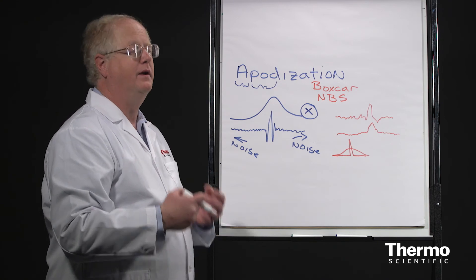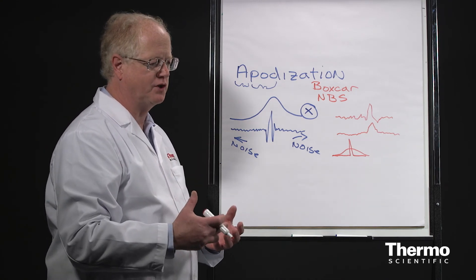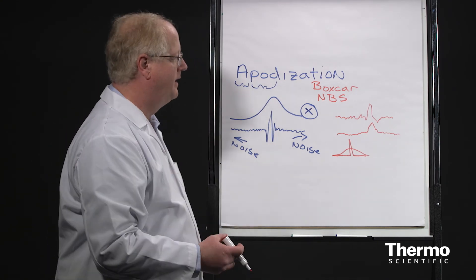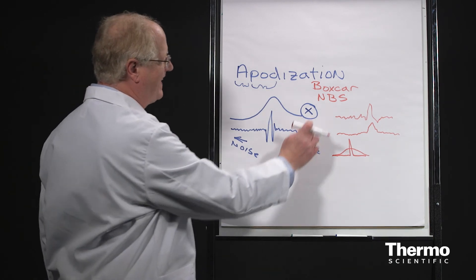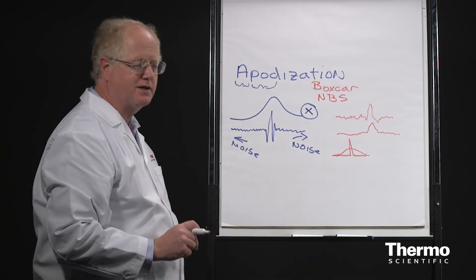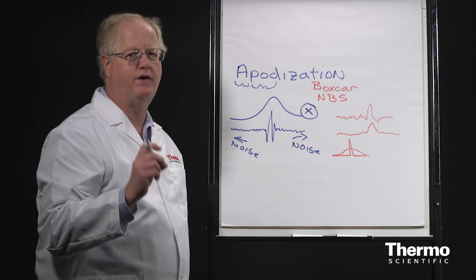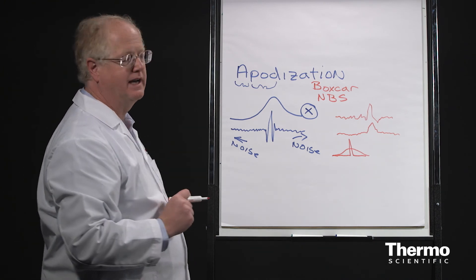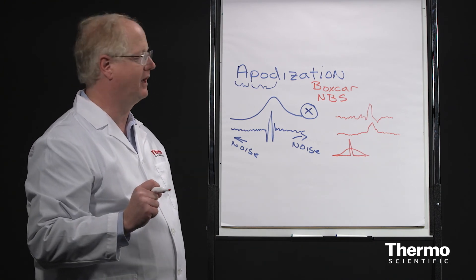And again, the manufacturers set those up so that there's already a default chosen that makes that decision for you. In the case of gases, however, you may need the boxcar because you're going to need those very narrow line widths. And that's the example we'll look at next when we go into the lab with this.